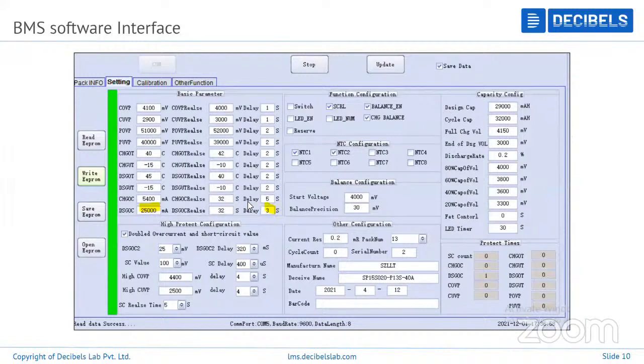So that was the basic protection level. These smart BMS also have a second layer of protection called high protection configuration - this activates when there is more inrush current than the values you have set, to avoid any short circuit, through both hardware level and software level protection.